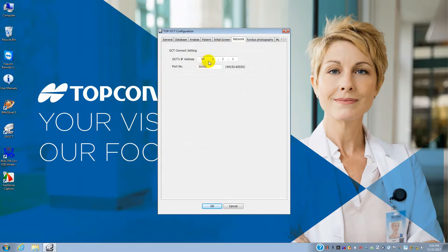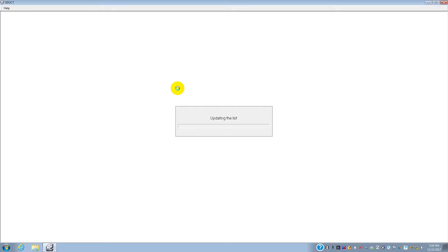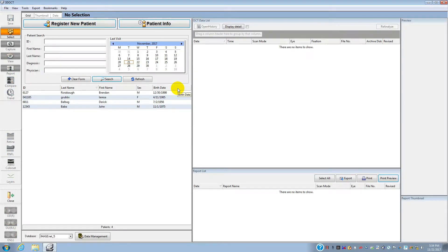Make sure it says 10.1.1.1 — that's the OCT's IP address, what you entered on the first screen. Make sure the port number is still 50,001, then click OK. When you click 3D OCT it should connect to the OCT, it should say 'Updating the list,' and you should get your main screen. That's how you set the IP addresses to match everything so it will work perfectly.